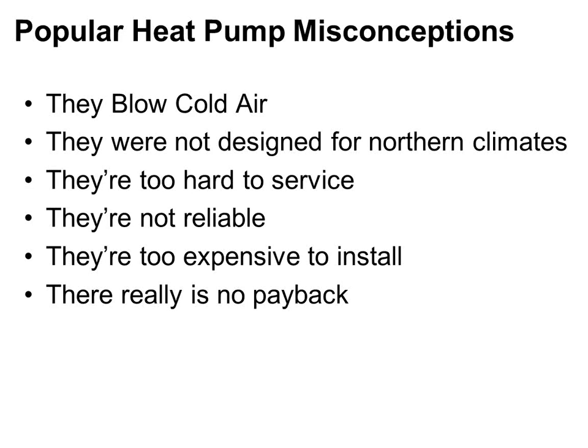When I turn any mechanical device on, fan, compressor, whatever, it heats up and cools down the metal, right? Every time I heat something up and cool it down, it expands and contracts. Well, because I have dissimilar metals inside the compressor, outside the compressor, in the coils, and all these different things, the different metals expand and contract at different rates. So the more I heat them up and the more I cool them down, generally the more likely they are to fatigue and break. If I have variable speed equipment, as you'll see in a little bit, I tend to run it continuously. And I just kind of ramp it up and down a little bit, but it's still running, and it's not turning on and off. And it's not heating up and cooling down as much. And generally, these things tend to last longer.